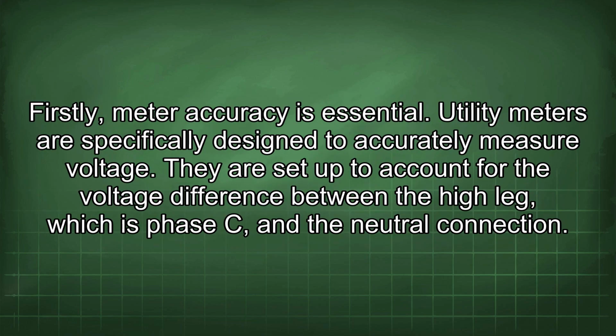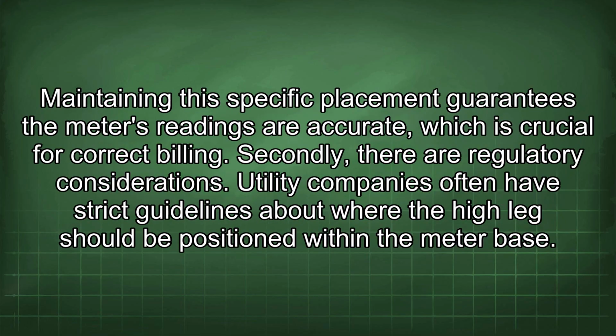Firstly, meter accuracy is essential. Utility meters are specifically designed to accurately measure voltage. They are set up to account for the voltage difference between the high leg, which is phase C, and the neutral connection. Maintaining this specific placement guarantees the meter's readings are accurate, which is crucial for correct billing.